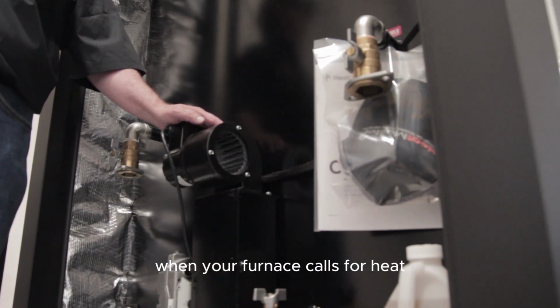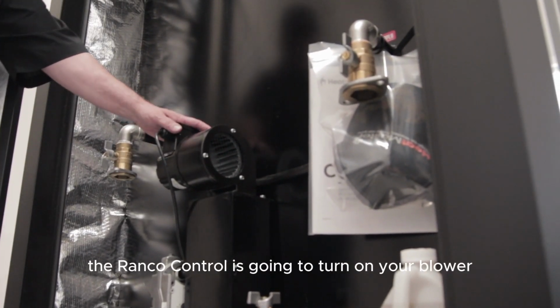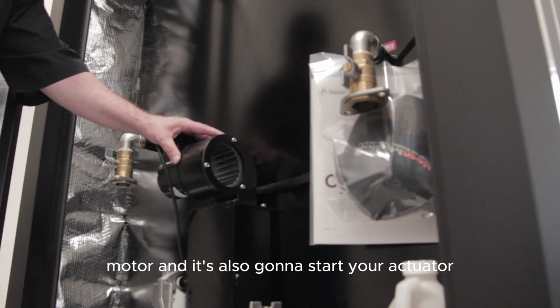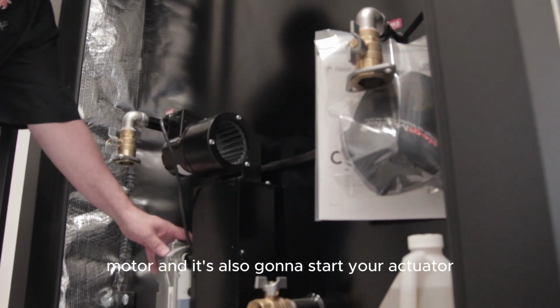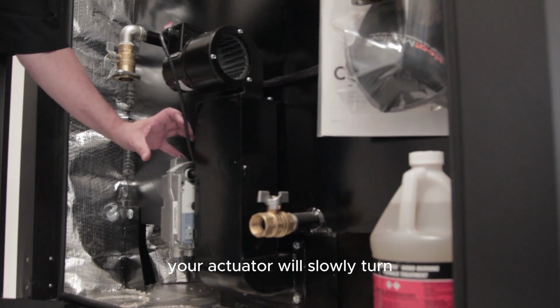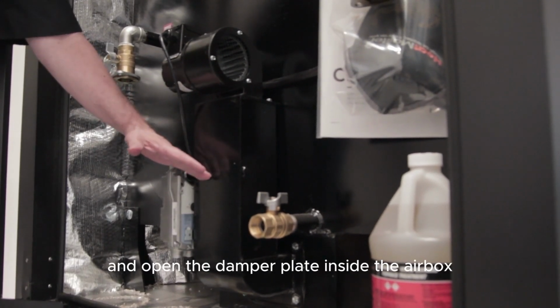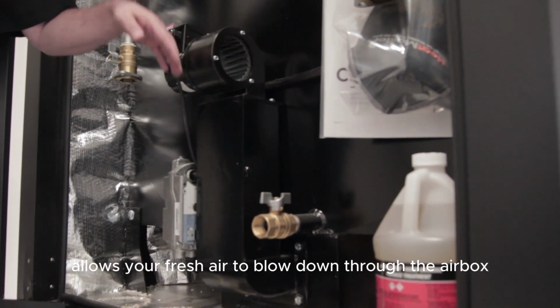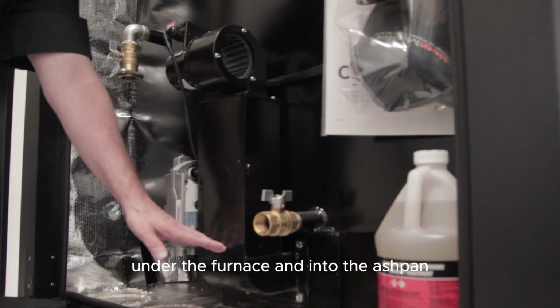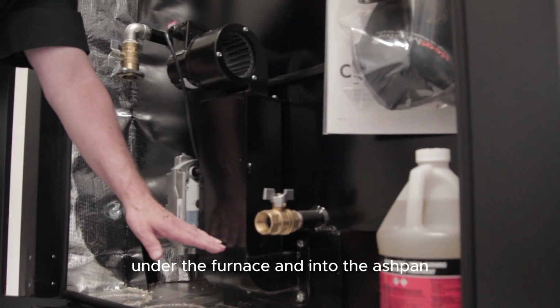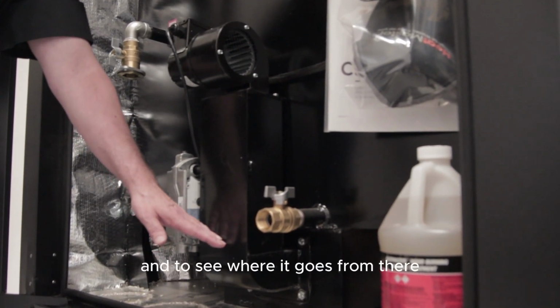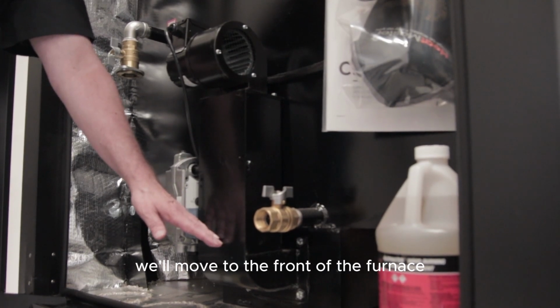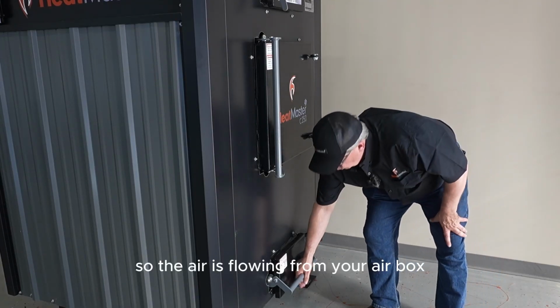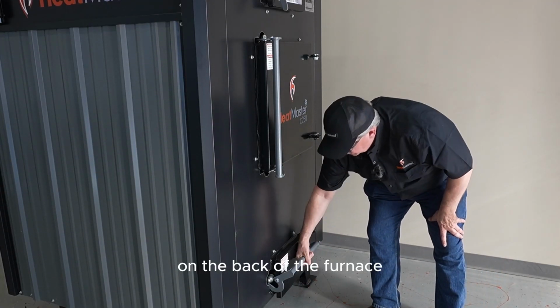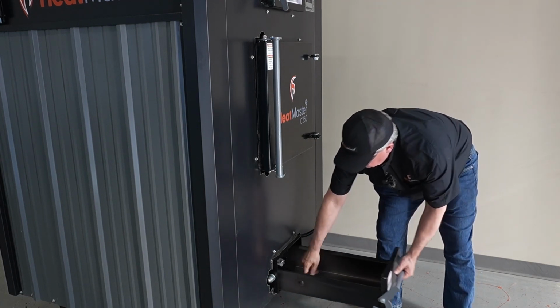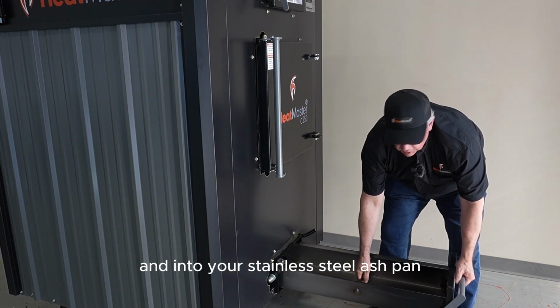When your furnace calls for heat, the Renco control is going to turn on your blower motor, and it's also going to start your actuator. Your actuator will slowly turn and open the damper plate inside the airbox. This allows your fresh air to blow down through the airbox, under the furnace, and into the ash pan. And to see where it goes from there, we'll move to the front of the furnace. So the air is flowing from your airbox on the back of the furnace and into your stainless steel ash pan.